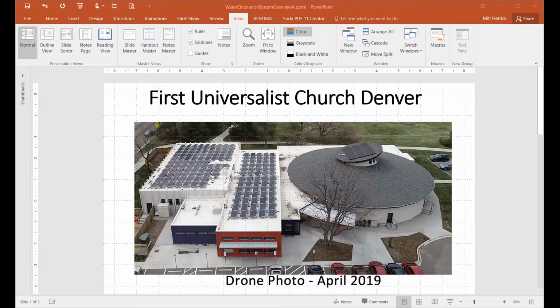There are a total of 10 different heat pump furnaces throughout the facility. There are 3 in this round portion in the basement, and the rest of the 7 are in this flat portion in the basement. The sum of all the furnaces totals about a 35-ton rating. So that's what the so-called ground loop heat exchanger, which was installed in the north parking lot, which is off to the right here. You can't see it in this photo, but there are 12 boreholes that were drilled vertically in that parking lot, and then black plastic U-shaped pipe was put down into each of the boreholes to exchange thermal energy between the earth and the building.